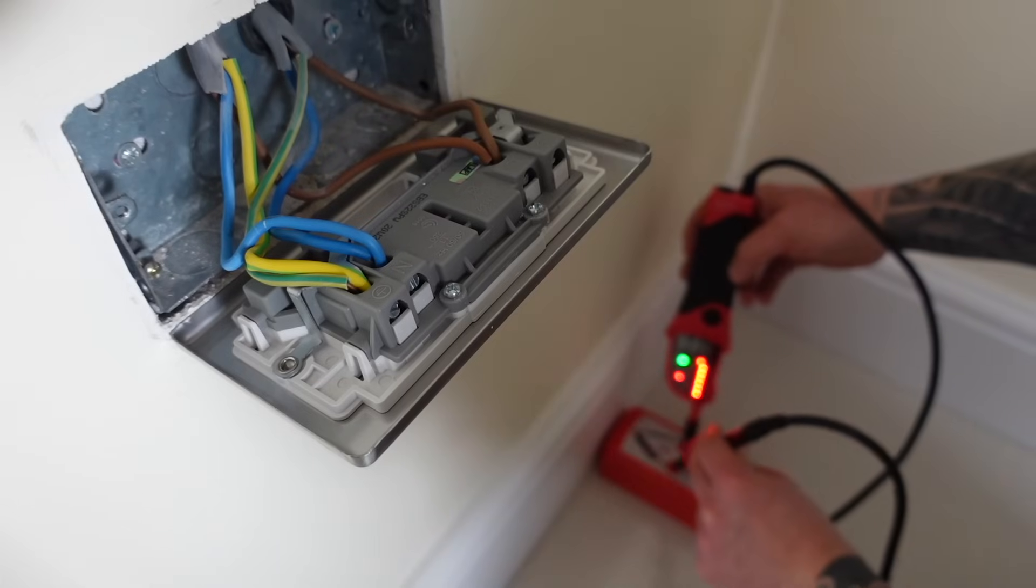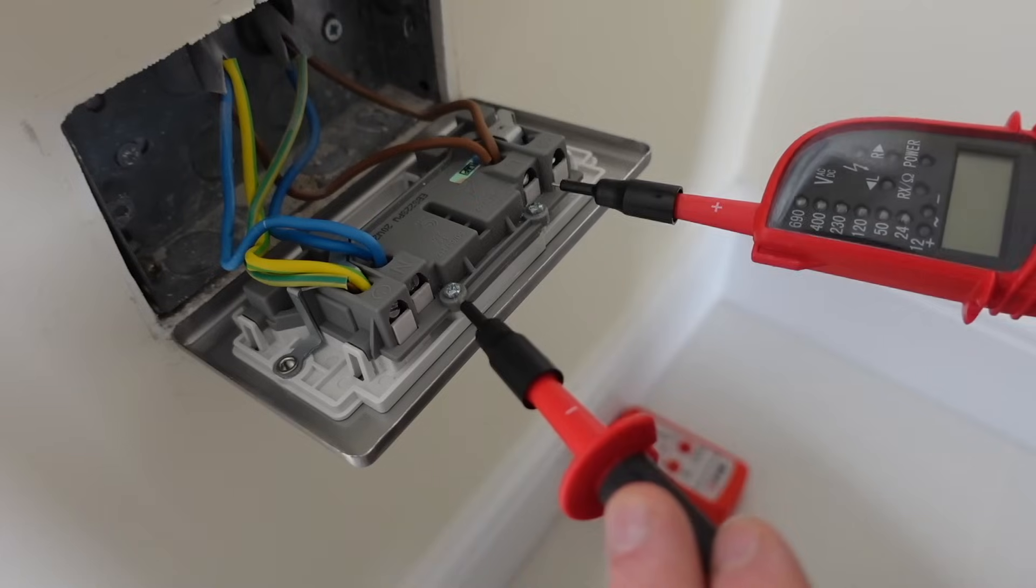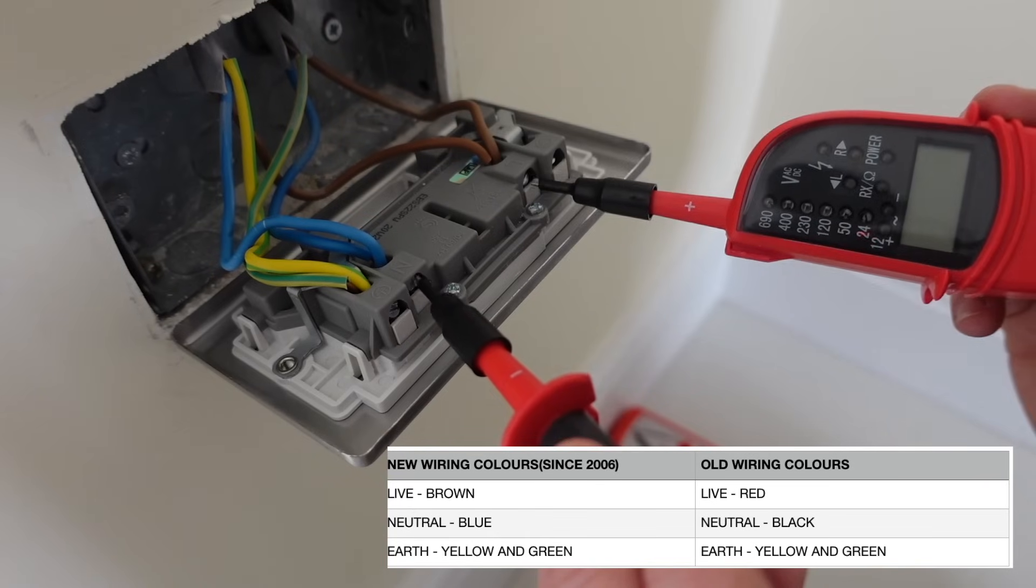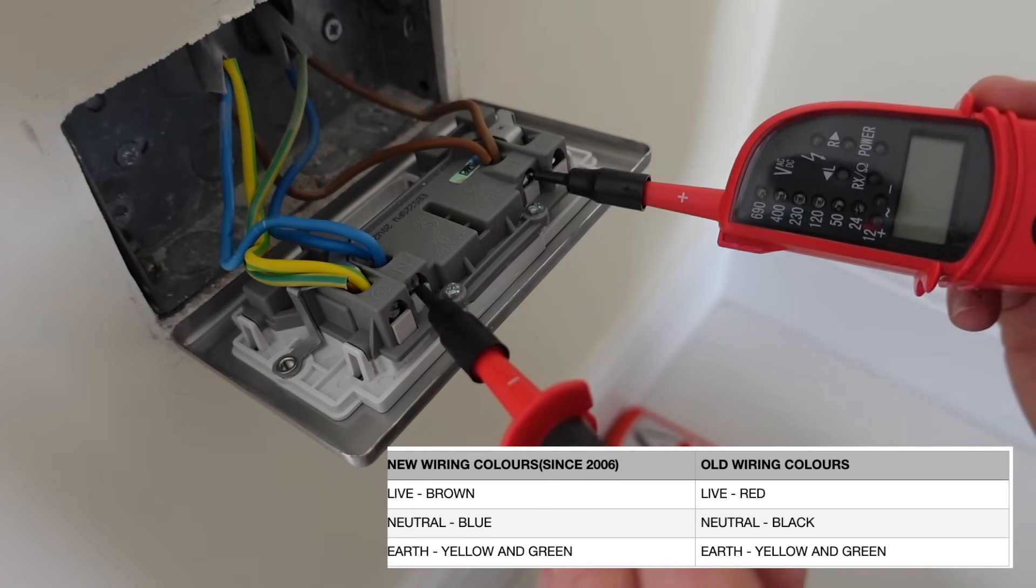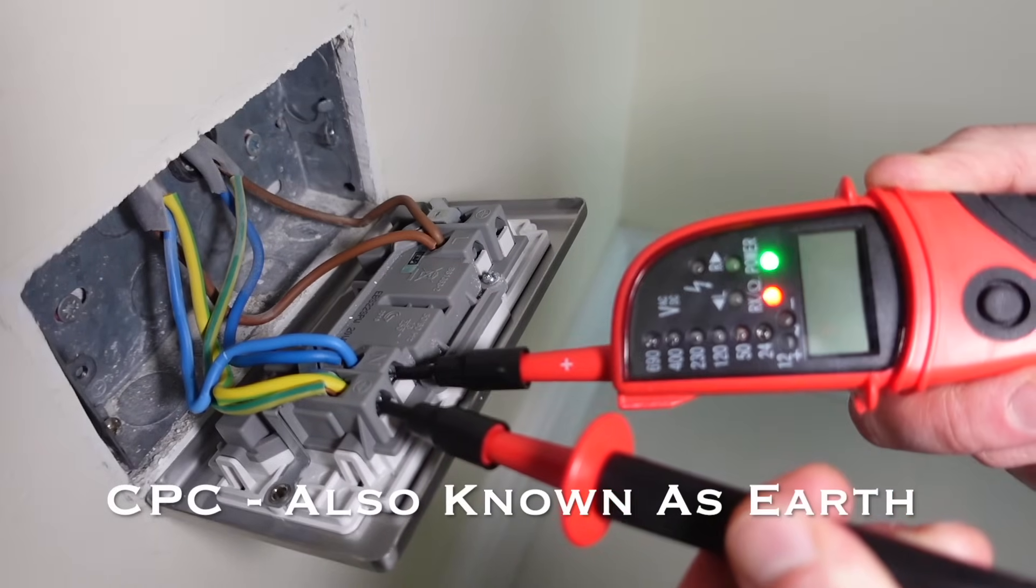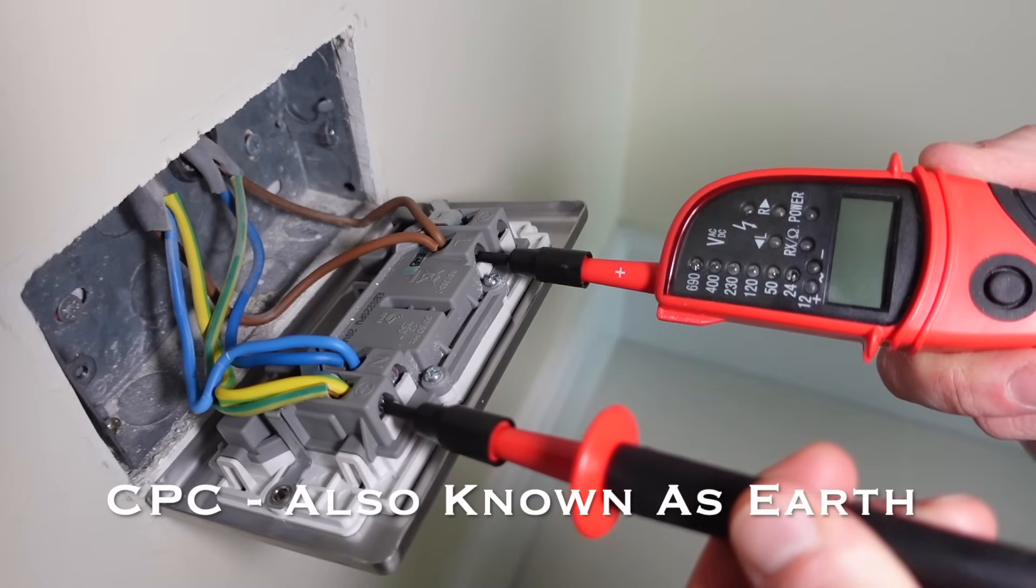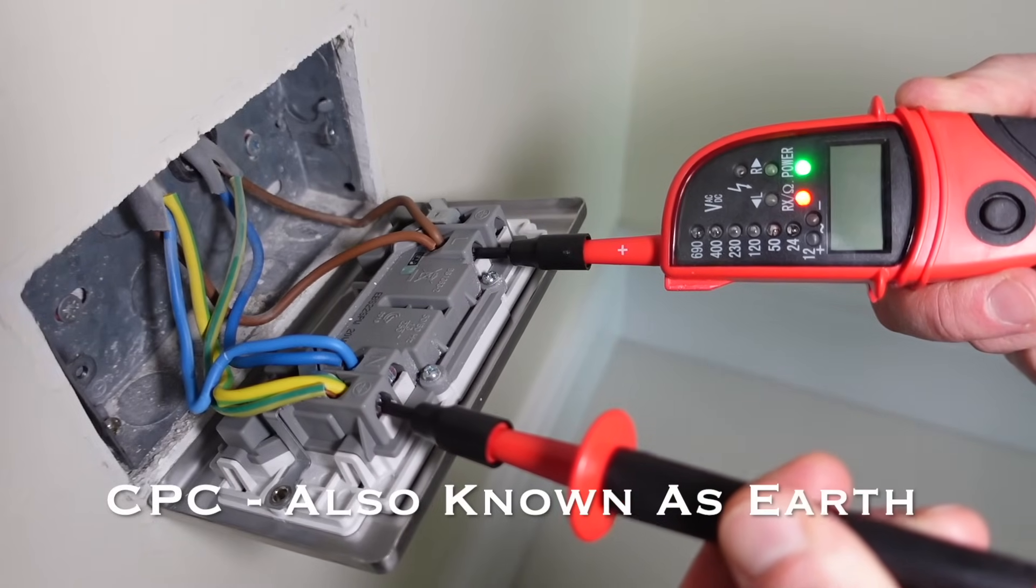First of all we check our voltage tester on the proving unit. We then check between the live or line, depends what you want to call it, and you'll see that all we'll have here is continuity. We have no voltage being displayed. CPC to neutral, that's dead. And we're going to test CPC to live and that's dead as well.